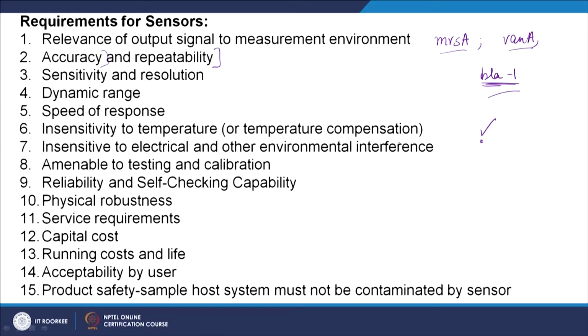Now, one thing is there in a country like India and many countries around the world, we have temperature variability in both diurnal cycle and also seasonal cycle. So, for example, where I am right now in North India, in Uttarakhand, in winter the temperature might fall down to below 5 degrees Celsius, and then during summer we might stay consistently 46 degrees Celsius plus, which is quite a big range of temperature. So, my sensor should not fail at these extreme ends. It should not go kaboom at 48, 49 degrees Celsius, or it should not stop working at very low temperatures.